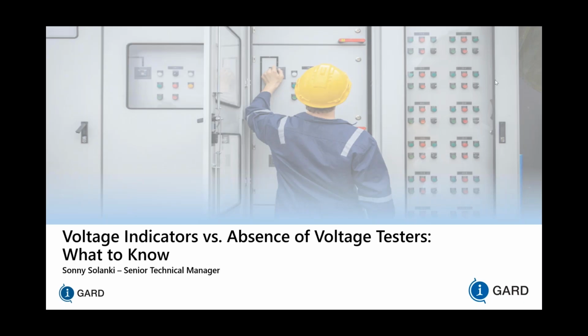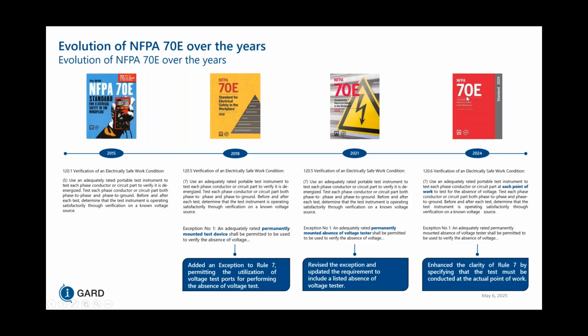Today's presentation is going to be on voltage indicators versus absence of voltage testers and what you need to know. So just to start off, NFPA 70E is a standard for electrical safety in the workplace. And in the 2015 iteration in section 120.1, rule number 5, it indicates that an adequately rated portable test instrument can be used to test each phase conductor or circuit part to verify it is de-energized. This is where they test phase to phase and phase to ground to confirm absence of voltage.